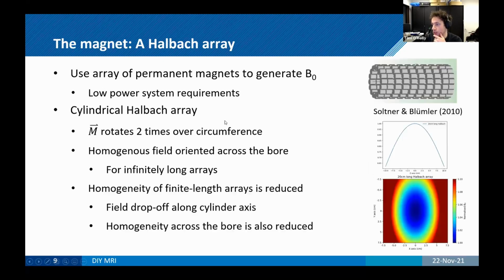But obviously, we can't make infinitely long Halbach arrays. So what we find is that the homogeneity is actually significantly reduced when you reduce the length of the system. It has 2 consequences. Your field will drop off along the length of the bore. So this is just a plot of the field basically along this axis here. So you get a very strong drop off, but you also, in plane, get quite a high inhomogeneity with this very characteristic ellipsoidal isocontour.